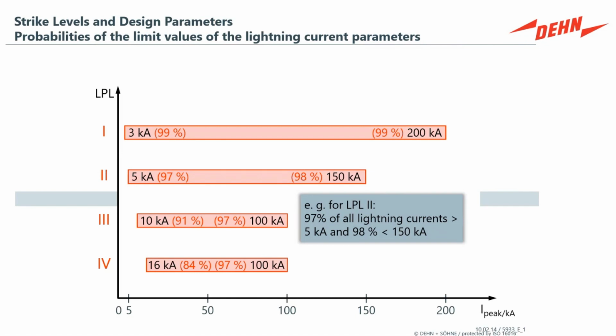So the worst case scenario is that you've got a very high lightning current up to 200 kA and a very low lightning current, 3 kA, which defines a small radius of the rolling sphere. The more lenient type 3 level, LPL level 3, which is much more in line with an NFPA standard, is defined as 100 kA of lightning current. So your connectors have to be able to withstand the lightning current. And the 10 kA lower level defines a more relaxed radius rolling sphere, a larger radius, a little bit bigger spacing between lightning rods, essentially, is what it allows.